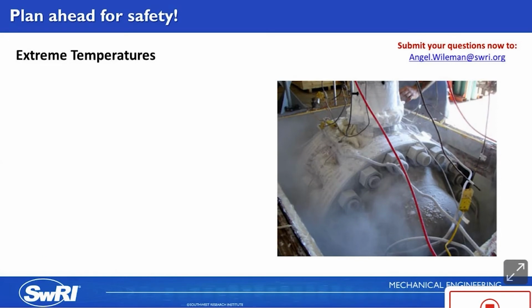Another hazard associated with fugitive emissions testing is the extreme temperatures. Temperatures range from cryogenic temperatures that require liquid nitrogen cooling up to 750 degrees Fahrenheit or higher, really, depending on the qualification range. To address this concern, you want to make sure, again, all of your plumbing components are rated for the temperatures. You want to wear the proper PPE whenever you're handling liquid nitrogen or approaching the valve for leak testing measurements. I would recommend safety glasses, a face shield, gloves that cover a majority of the arms, and long sleeves. And make sure that the gloves you select are designated for thermal protection.